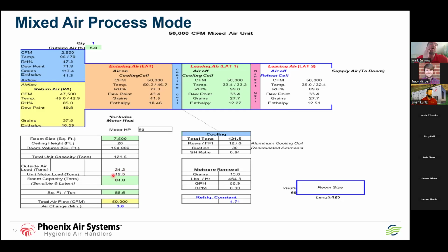This is easy math, right? A 50,000 CFM unit has a 50 horsepower. A 10,000 CFM has a 10 horsepower. It's basically a straight line ratio is all it is. Bottom line for the room, as if to say we were going to hang ceiling hung units, would be about 84.8 tons. Okay, that's the load.